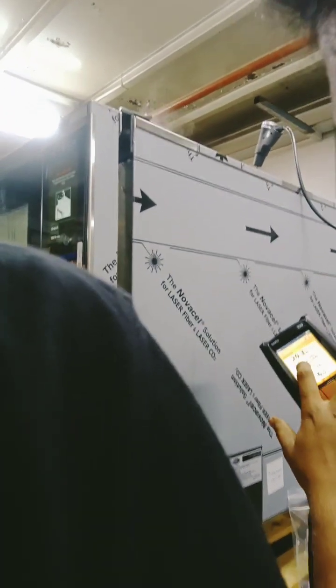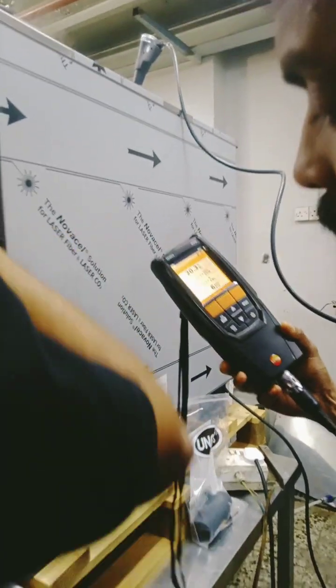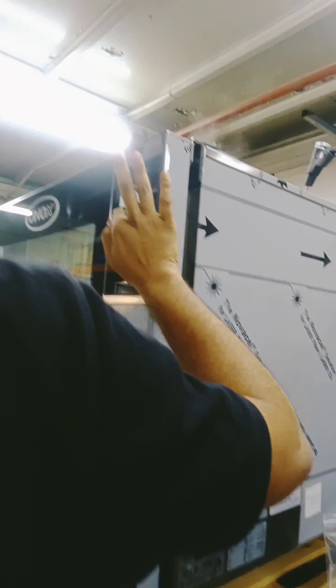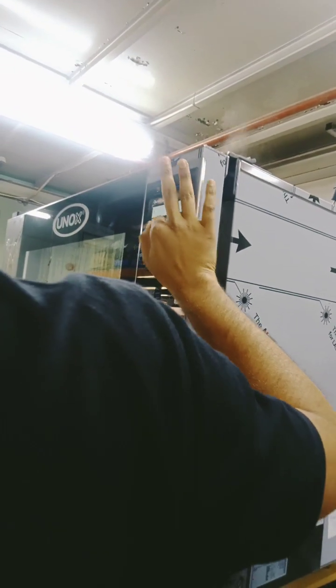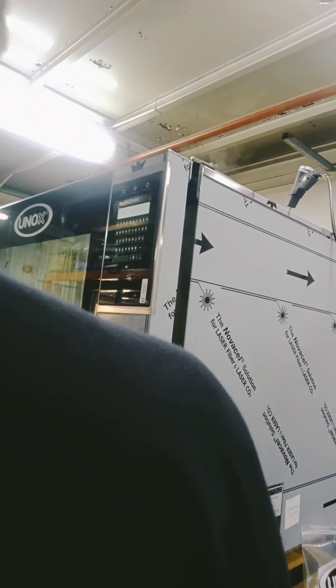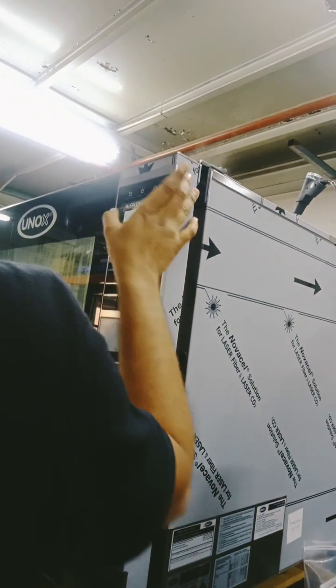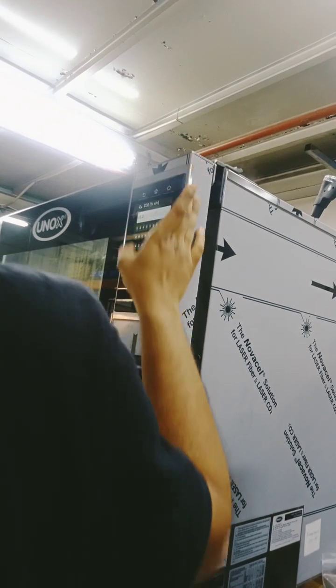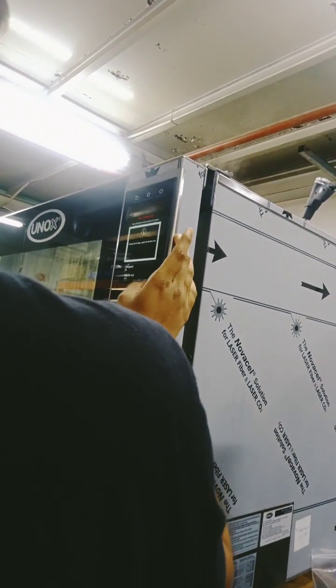That Testo, once I show the value, the Testo value. For example, someone doesn't know the value. They put like 35 because it should be below 30, right? And this one, as per our chart, should be 11.8. I'll put 11.2. Okay. If I press continue, value is out of range.